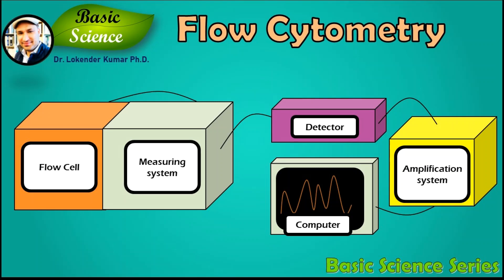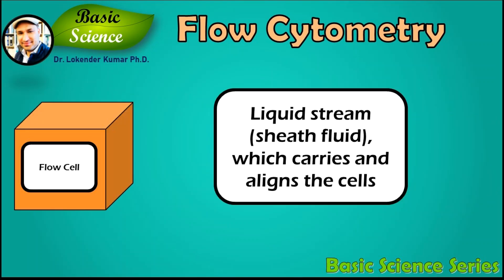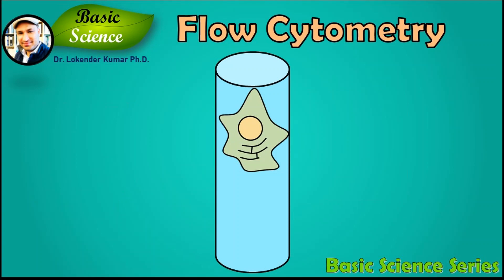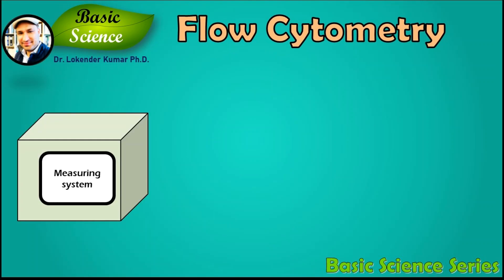The flow cell has a liquid stream called sheath fluid, which carries and aligns the cells so that they pass as a single file through the light beam for sensing. The measuring system commonly uses measurement of impedance or conductivity.